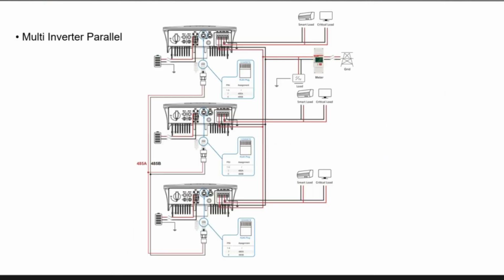Any other questions, anything else? The cables from the battery, they are 10 square millimeter. Sleeves with it for 10 millimeter. You can put it in the back. It depends which battery manufacturer you actually use. Yeah, there were some oversized cables. We experienced that problem as well. We actually got some replacement cables, or we cut down some of the cables on there because the size of the cable was far too big, oversized for the discharge current of the battery anyway. So it didn't matter if we just chopped a few of the strands off it. That's what we ended up doing. That was on an early delivery, I think. Shouldn't have that problem now. But yeah, good point. They won't fit in with the sleeves. Your breaker. But not anymore.